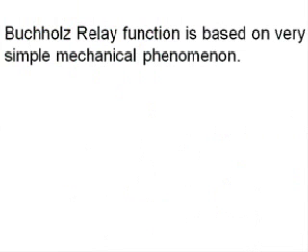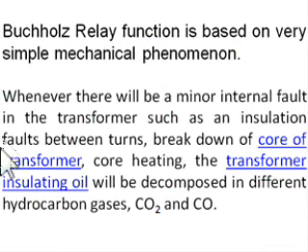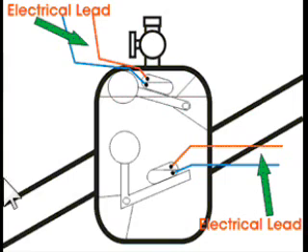Buchholz Relay function is based on very simple mechanical phenomenon. Whenever there will be a minor internal fault in the transformer such as insulation faults between turns, breakdown of core of transformer, core heating, the transformer insulating oil will be decomposed into different hydrocarbon gases, CO2 and CO.